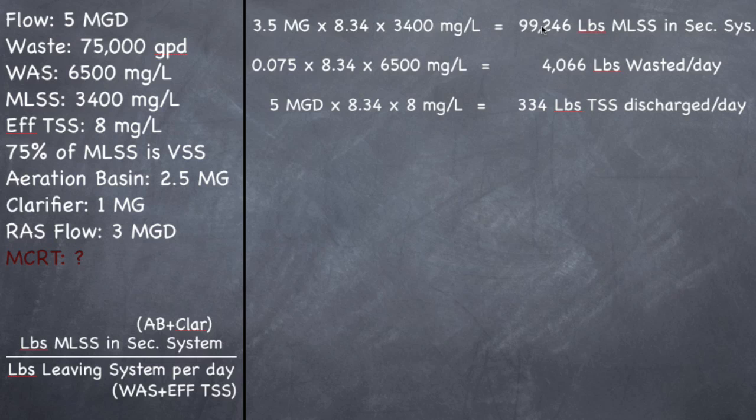So we've got the top part of the formula. We need to add these two together to get the bottom part of the formula. It's WAS plus effluent TSS. When I add 334 plus 4,066, you should get 4,400 pounds leaving per day. That's how much is leaving your secondary system total per day.